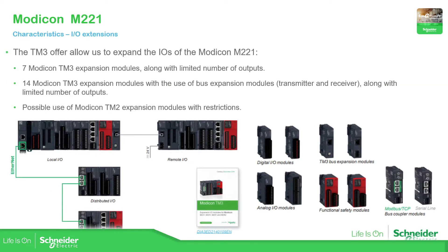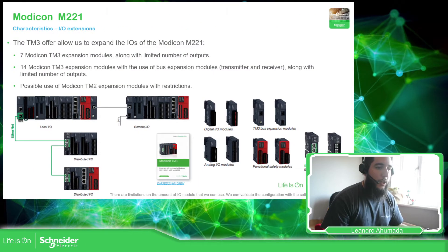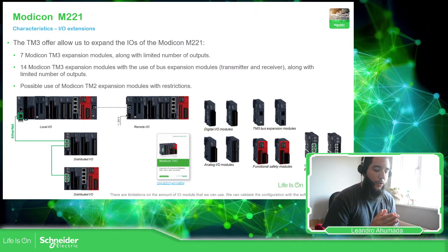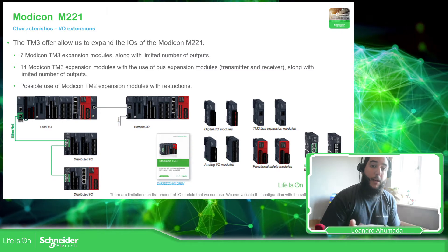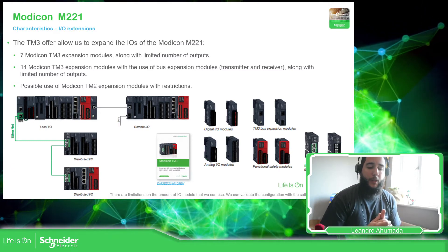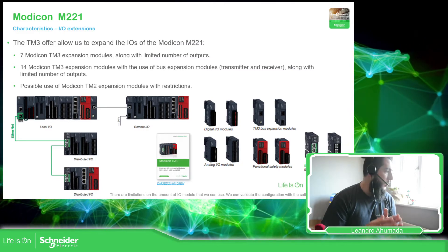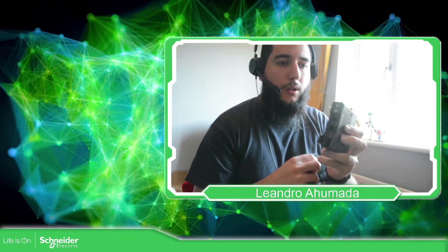If we don't have enough I/Os, we can use expansion modules. The expansion modules are the TM3 family, but we can also use a bus coupler to extend the I/Os of the PLC. Here we have the TM3 modules, and the bus coupler — in this case for Modbus serial communication — and we also have one for Ethernet communication, Modbus TCP.